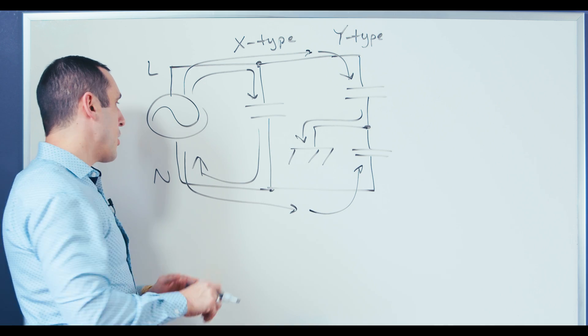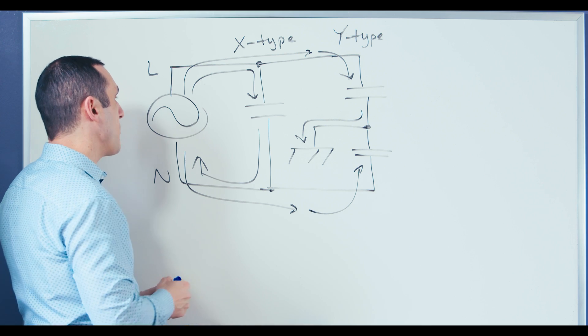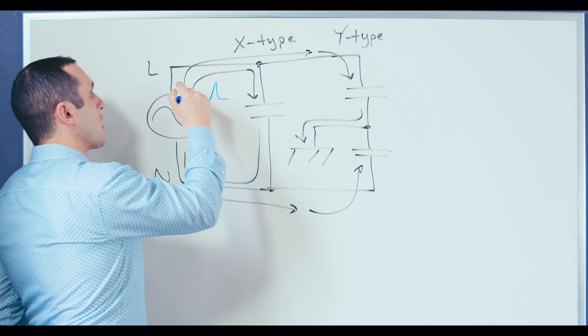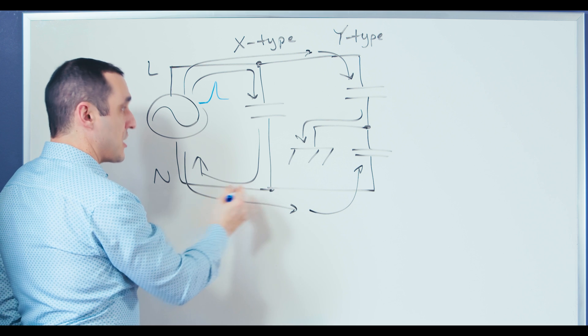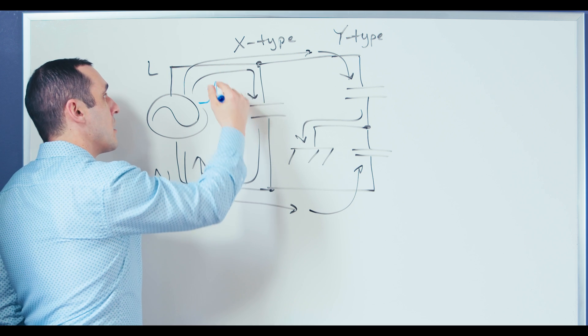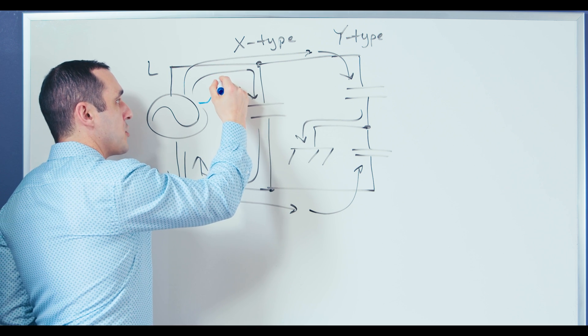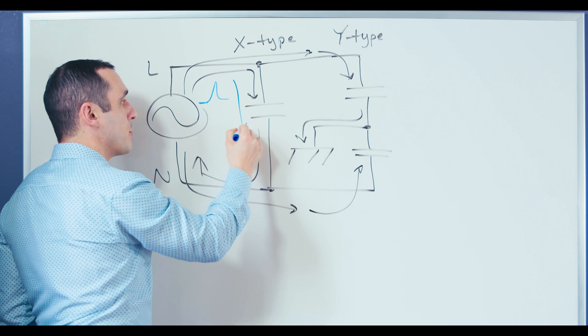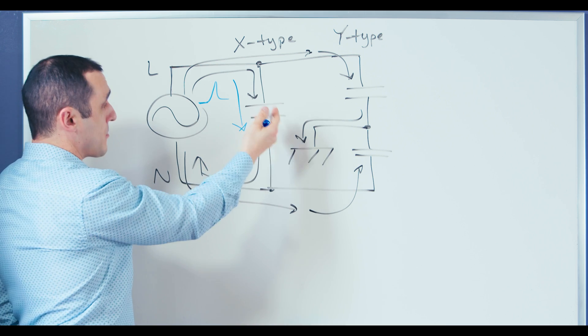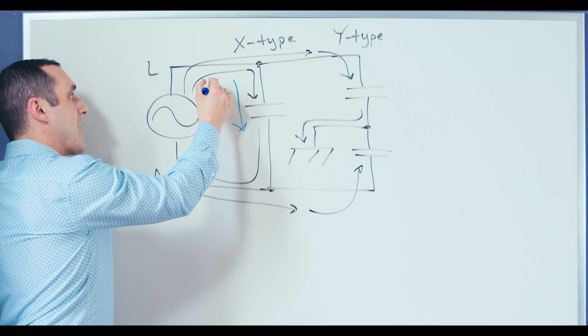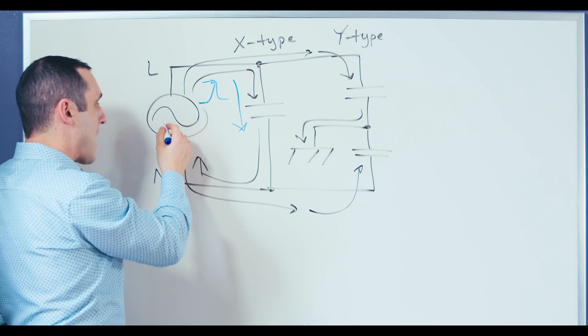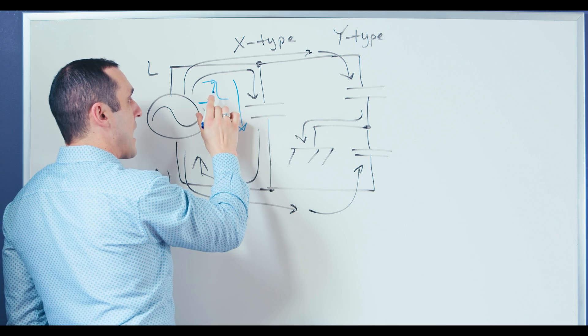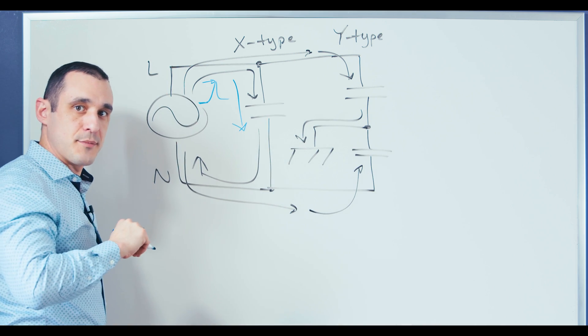So let's suppose on the line we have a pulse that comes in and starts propagating along this wire. Here we have essentially ground while this line is carrying signal. So this line is then going to allow this pulse to pass through this capacitor and if this capacitor has high enough withstand voltage, it can withstand this peak voltage from this pulse and then pass that back to ground rather than allowing this pulse to pass through to the other end of the system.